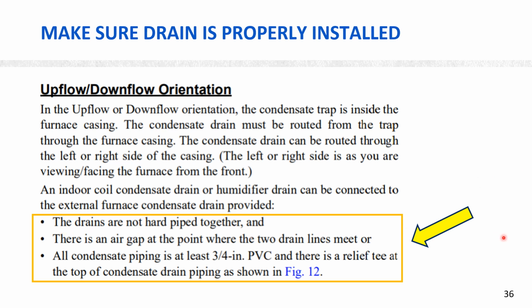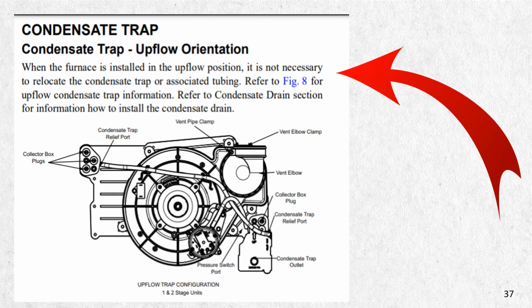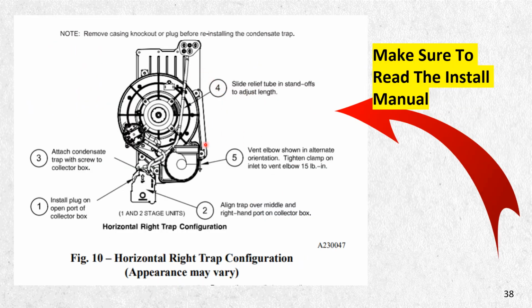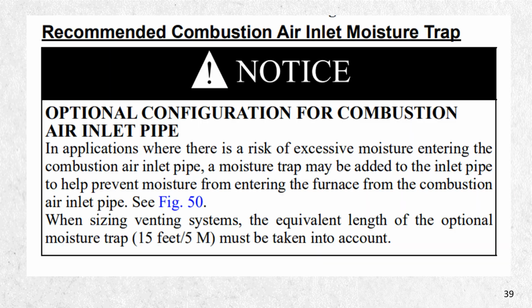Always make sure if you're in the upflow or the downflow, the drains are not hard piped together, and make sure you're using 3/4 PVC and you leave an air gap. On the condensate trap, it's kind of all self-explanatory. If you just go into the install manual and look, it'll tell you where this hose hooks in, where it travels down to and hooks in, where this one goes, and then out your condensate trap here. And it has different setups for the horizontal right. This is how you would run it. Horizontal right, make sure this is pointing up in the horizontal position, and then make sure you read the install manual on those.